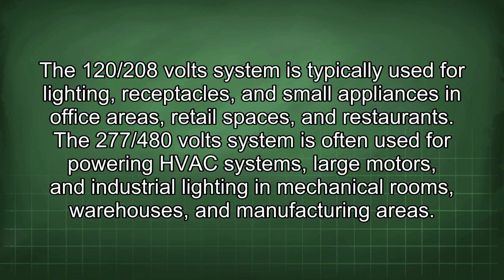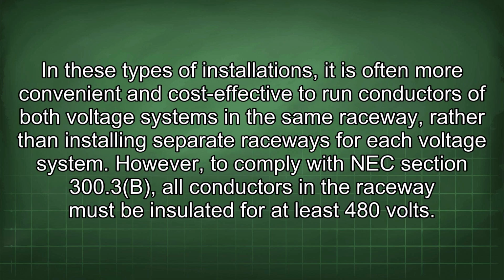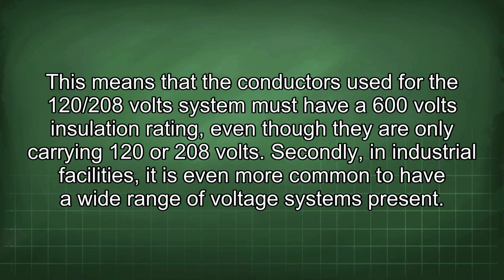The 277/480 volt system is often used for powering HVAC systems, large motors, and industrial lighting in mechanical rooms, warehouses, and manufacturing areas. In these types of installations, it is often more convenient and cost-effective to run conductors of both voltage systems in the same raceway, rather than installing separate raceways for each voltage system. However, to comply with NEC Section 300.3b, all conductors in the raceway must be insulated for at least 480 volts. This means that the conductors used for the 120/208 volt system must have a 600 volt insulation rating, even though they are only carrying 120 or 208 volts.